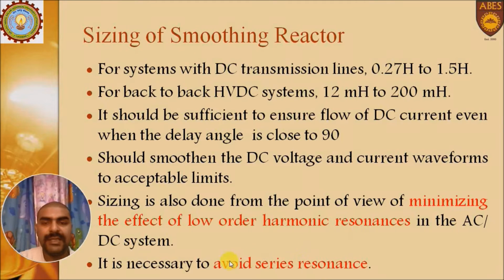It can avoid the resonance condition if the inductance value is selected in such a way that it would not result in resonance. At resonance, if series resonance is there, then there will be a sharp rise of current, which may increase the stress on the converter valves.